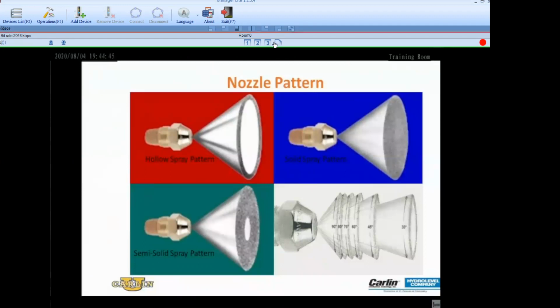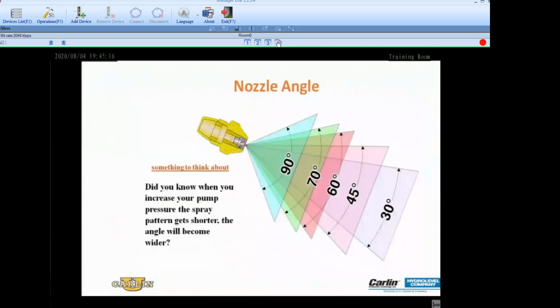Well, most will tell you that they're trying to match the combustion area. So a wide area, short and wide, they're thinking 70, 80-degree nozzle. A long combustion chamber, now they're thinking 45-degree nozzle. And although that sometimes is true, the nozzle pattern and spray angle has less to do with the dimensions of the combustion chamber than it does to the air pattern that exits the front of that burner. You have to match the air pattern.